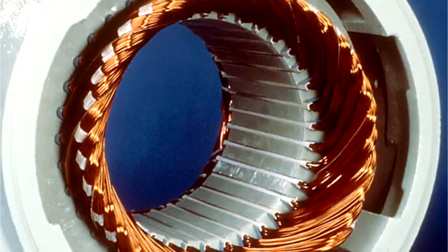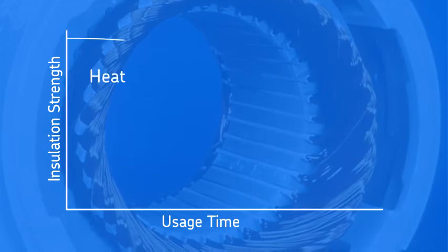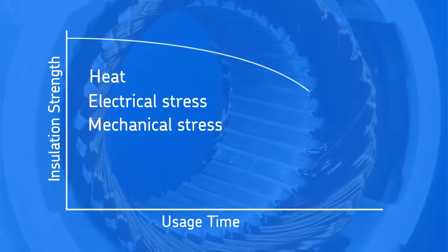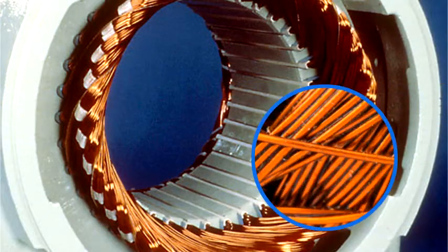Let's take a quick look at the motor insulation system. Insulation strength degrades over time due to heat, electrical stress, mechanical stress, abrasion, and contamination. The most common insulation failure is between turns of wire that are next to each other in the same coil.